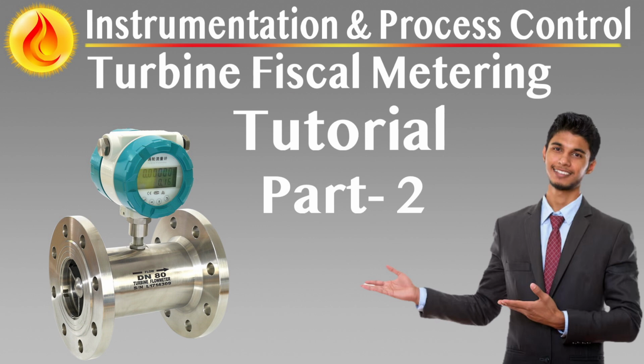Field equipment must be laid out to support safe operation and maintenance in all conditions, with all wiring glands, seals, and terminations protected against water ingress, UV degradation, and vibration. Environmental and electrical resilience at the field level is essential to preserve the accuracy, uptime, and safety of the entire fiscal metering system. Instrumentation and electrical, operational resilience, environmental compatibility, and system integration.